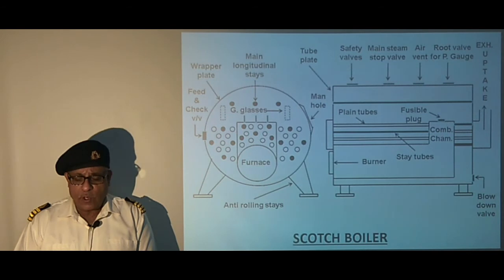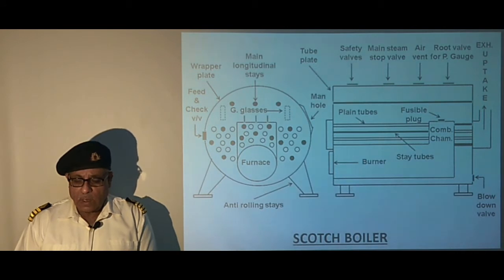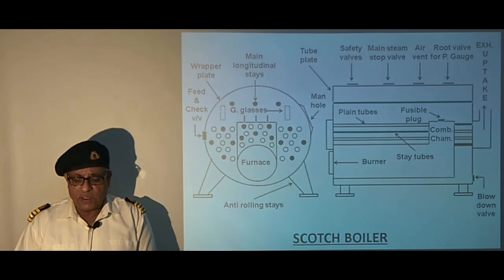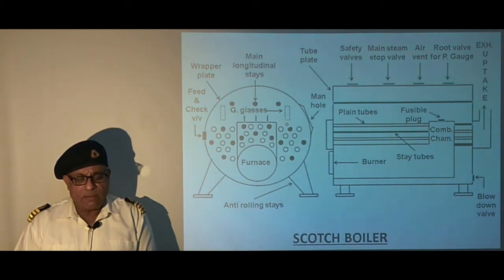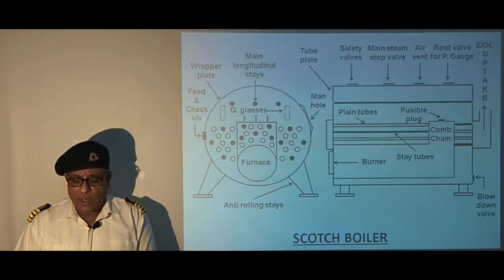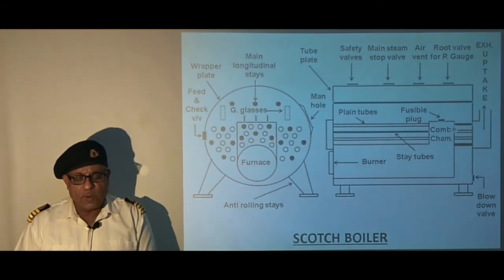Gauge glasses are mounted on the front tube plate, and their bottom connection is a minimum of 5 inches above the top of the combustion chamber. The crown of the combustion chamber is fitted with a fusible plug to prevent damage to the tubes due to shortage of water.